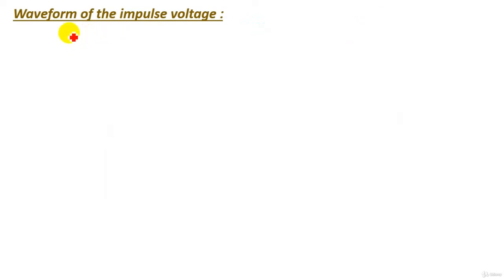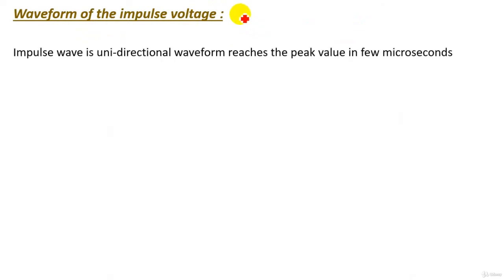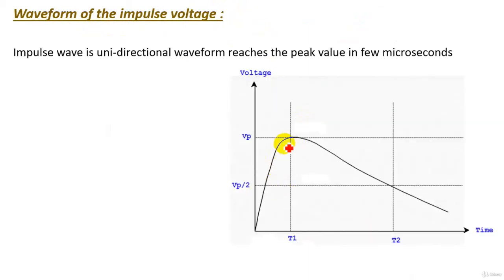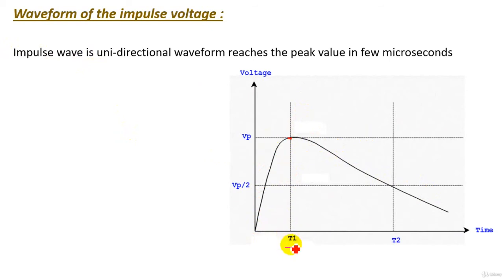Now let's understand the waveform of impulse voltage. When lightning strokes occur, the insulator or high voltage component is subjected to the impulse voltage waveform. This waveform is unidirectional and reaches the peak value in a few microseconds. The time it takes to reach the peak value is called the rise time.